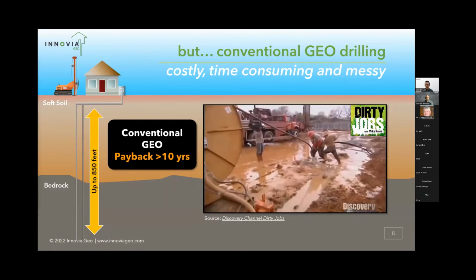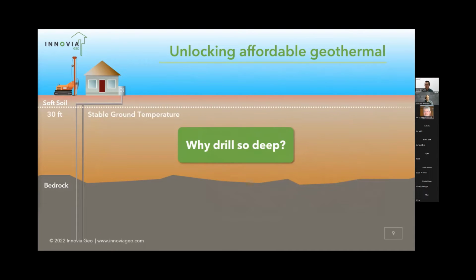Although a geothermal system is extremely efficient, the payback versus conventional HVAC systems can usually take more than 10 years. This is not being critical of the performance or the benefits of how conventional geothermal systems are installed. It's just by nature of the process and cost that they take a long time to recover that investment. So a question my partner and I asked ourselves 3 years ago when we first got into geothermal was, do we really need to drill so deep? Especially considering that ground temperature is stable all year round by about that 30-foot depth.